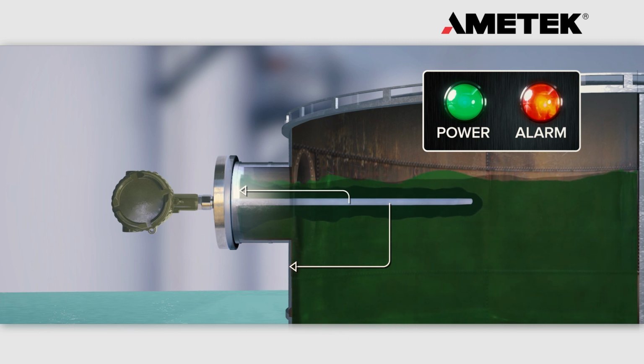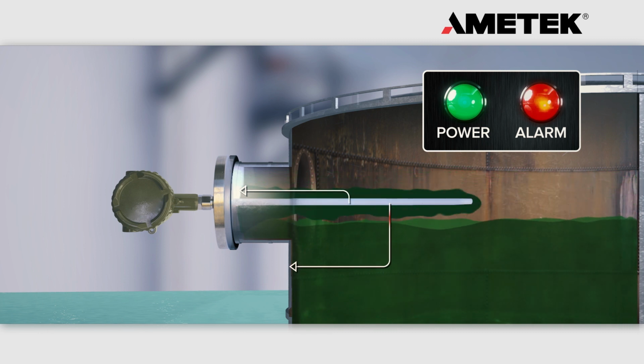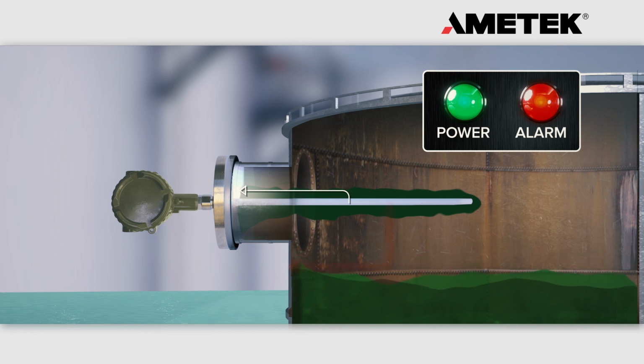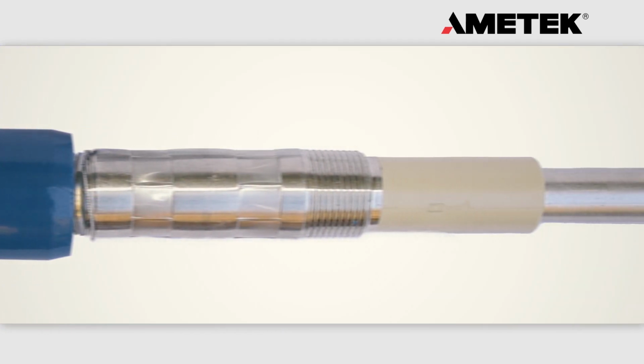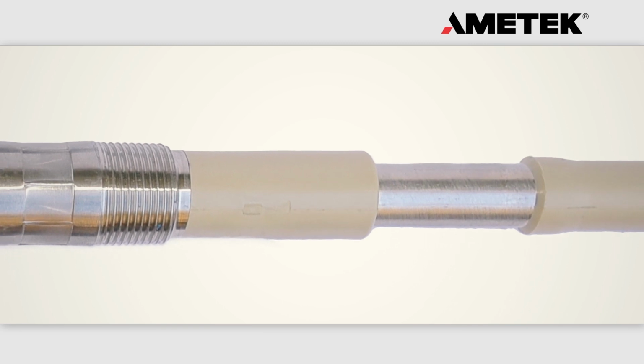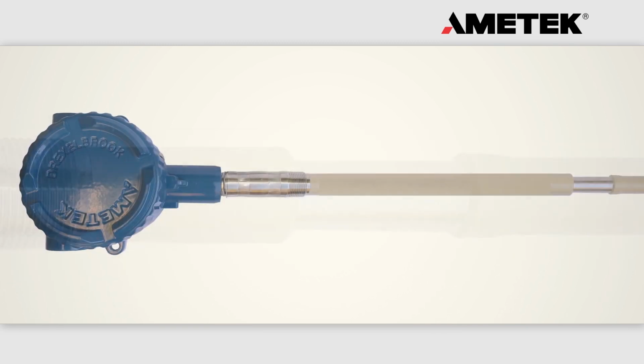As you can see, there are multiple paths that current can take, all going through the process media. When the liquid drops back down and leaves a coating, the current paths through the process material are broken. However, there is still a path to ground from the active probe back to the tank wall through the coating. This causes the electronics to maintain a high level of indication or false alarm when using a traditional two-terminal style probe. Drexelbrook pioneered the use of Cote-Shield technology as the solution to tackling this problem.